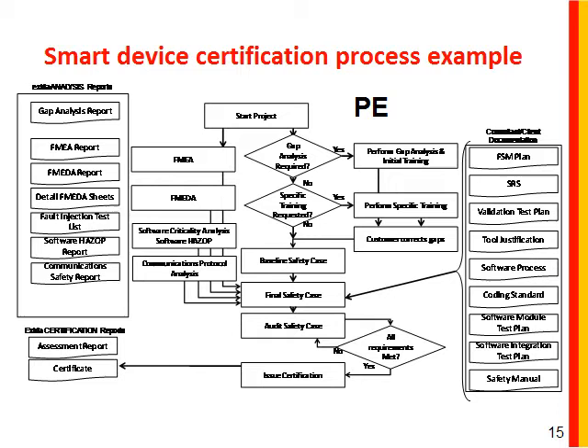Take a look at this drawing — it appears a little complex, but the essence is pretty simple. At exida, we analyze the process: how does a manufacturer create and test a new product? How do they write and test the software? What is the user documentation? We analyze the software, hardware design, systems-level design, and software design. We analyze any communication protocols for cybersecurity and for safety. We document all of this in a safety case — a technique that, as I've read, was developed by the British military a few decades ago — as a thorough and complete way to make sure a product meets all the requirements.